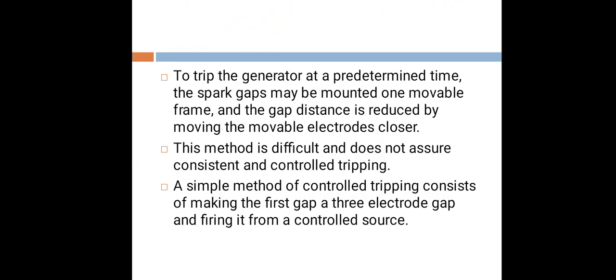To trip the generator at a predetermined time, the spark gaps may be mounted on a movable frame, and the gap distance is reduced by moving the movable electrode closer. This method is difficult and does not assure consistent and controlled tripping.